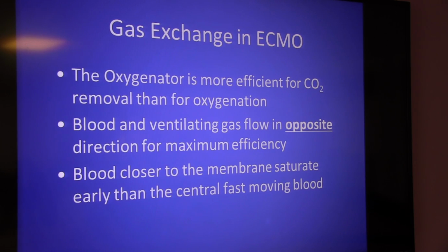Have you ever, Laura, had to use it? Yeah, no, I haven't had to do it here. But it was commonplace. But we also used to not wean the sweep flows so low. Now that we can go down to 0.1 liters, most of the time you can maintain normal CO2s.